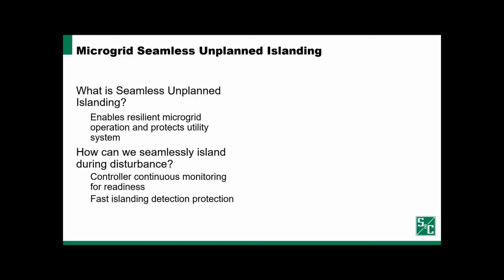One other technique and useful approach that I want to talk about is seamless unplanned islanding. Seamless unplanned islanding involves components of both control and protection that we've talked about here. Of course, when there is a fault or a loss of source on the power system, we need to ensure that we're disconnecting our resources to ensure that the fault gets de-energized and to ensure that crews can safely isolate and operate a system. If we need to disconnect our resources, and that is a permanent outage, our DERs also need to be available to supply an islanded system. How do we balance those needs to both disconnect and de-energize a fault, but also keep our DERs available to energize an islanded microgrid system?